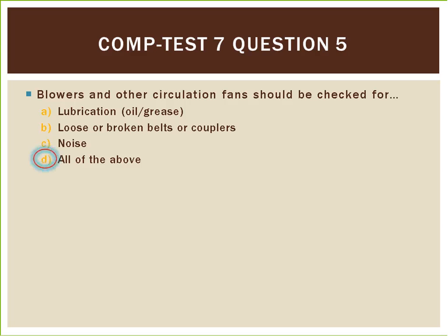A is correct because lubrication is one of the things that needs to be periodically checked on fans and blowers. B is correct because loose or broken belts or couplers are also part of things that need to be inspected periodically. And C is correct because noise is an indicator of a fan or blower problem and needs to be one of the things to be checked periodically. So answer D is the best answer here.